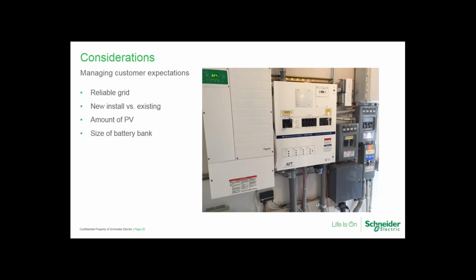When you're considering grid connected systems, determine how much backup power the customer needs. They may wish to back up the whole house, which is possible with up to 4 XW6848 units. Or if the customer already has a grid tie inverter, then AC coupling should not be an issue, but it's always best to check with the AHJ when installing a battery-based system. If the customer wants to back up a portion of the house, yet has multiple grid tie inverters, you can AC couple only 1 or 2 of those inverters, not to exceed the rating of the battery-based system, and dedicate the rest to the main service panel.